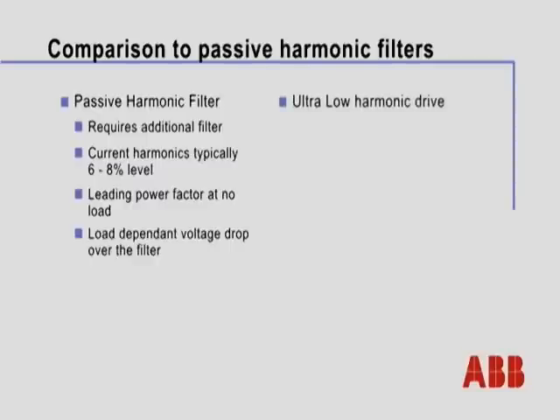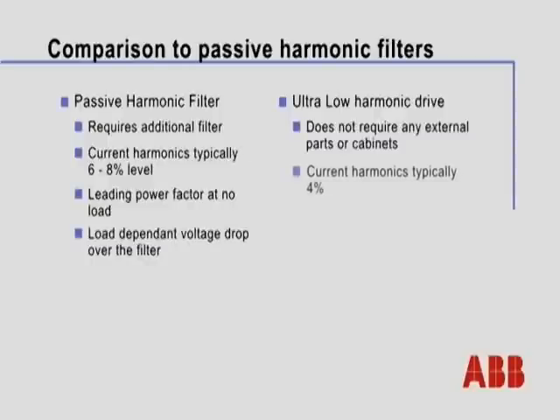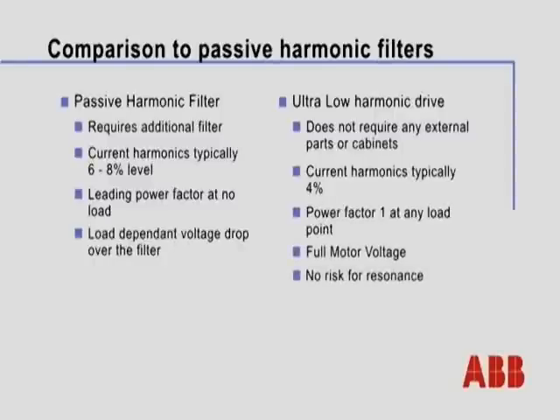Now, comparing that to the ULH, or ultra-low harmonic drive, we don't require anything external to the cabinet, and harmonic quality is typically 4%. Power factor is going to be unity, power factor of 1 in all distribution systems. We get full motor voltage, and there's no risk for resonance. So as you can see, comparing passive filters against the ULH, the ULH is the clear winner.